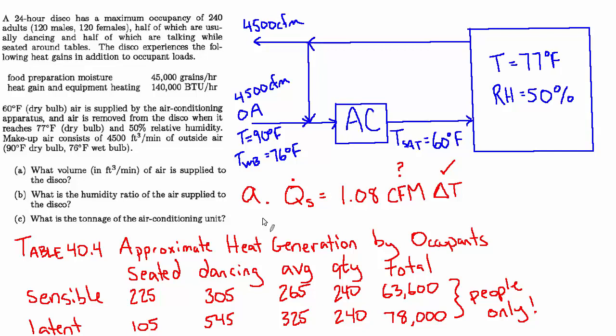It has to be dry enough to make up for this latent load that's in the space. However much moisture is being produced inside the room, some of that is going to be exhausted, some of it's going to be recirculated and conditioned. Ultimately, any moisture that's added to the space needs to be removed so that it could be a net effect of remaining constant, which is how it's keeping a relative humidity of 50% at that temperature. So it had better have a humidity ratio that's lower than what's in the room, and we have a way to calculate that.